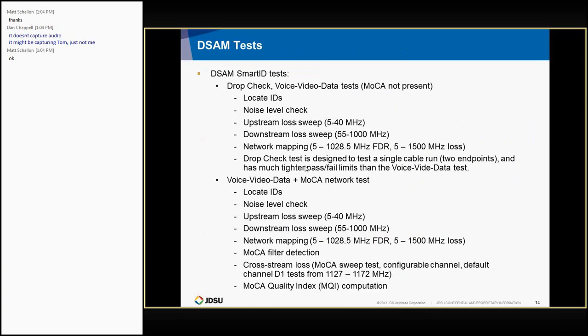Okay, the DSAM tests, these are the actual tests that are currently defined for the DSAM. There's a drop check and a voice video data check that don't include MoCA. They involve locate IDs tests, which I haven't described yet, but we'll get to that in a minute. Noise level check, an upstream loss sweep from 5 to 40 megahertz, a downstream loss sweep from 55 to 1,000 megahertz, and then the network mapping, which is a series of FDR tests and a loss test over a broad spectrum to look for filters and amplifiers.